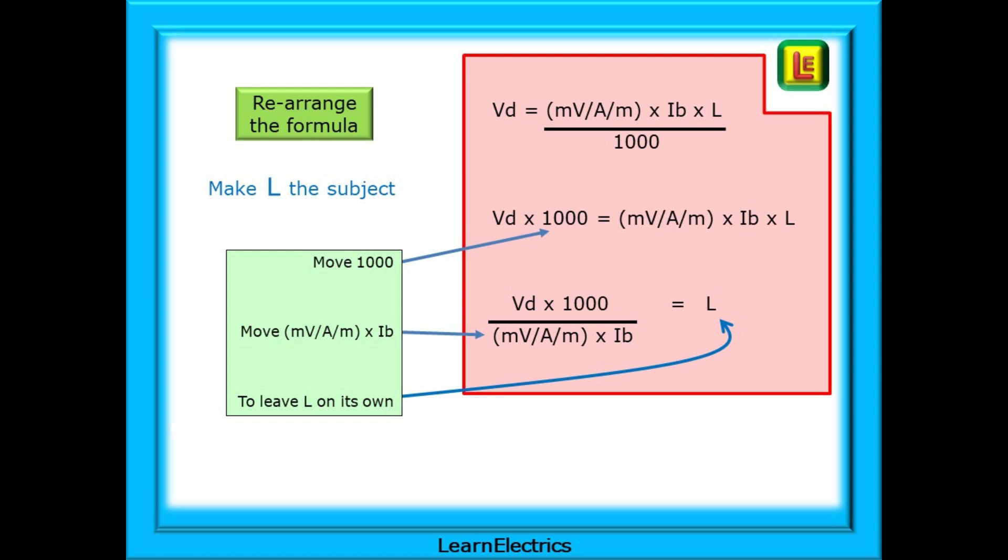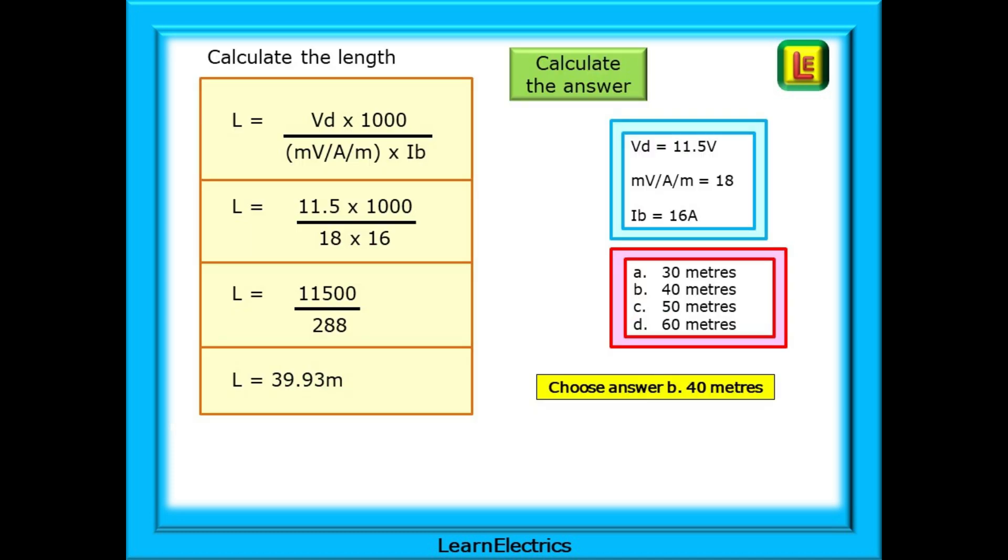And here is our very easy transposition. Move the 1000 from the bottom right to the top left. Then move mV/A/m and Ib from the top right to the bottom left. This now leaves L on its own. And that is how easy it is to rearrange the voltage drop formula. Now put in the numbers given in the blue box. Follow the working out in the yellow box and you should arrive at an answer of about 39.93 meters. Your answer might vary by a tiny amount depending on the rounding off, but it will always be very obvious which is the most appropriate answer. And for us, 39.93 is so very close to 40 meters that answer B has to be the correct choice.